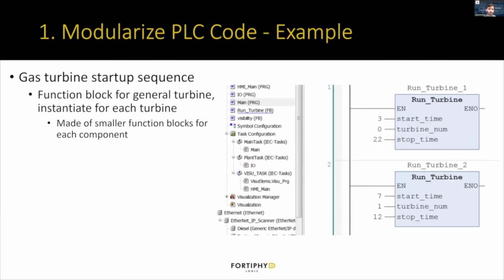So you can go through, have a function block for just a general turbine that fits the requirements for that turbine. And then you can instantiate it for each of the actual physical turbines. And you can even go deeper, as the previous presentation illustrated, just breaking that down into smaller pieces, smaller function blocks, maybe for each step of the startup sequence. And you can very thoroughly test each step of the sequence. You can then thoroughly test that single function block for that turbine, and be really sure that you handled all those corner cases really well, and make it a little bit harder for attackers to manipulate that and cause problems.